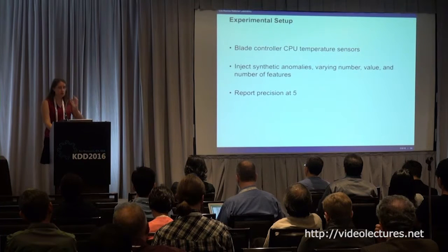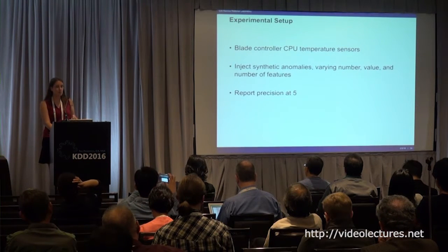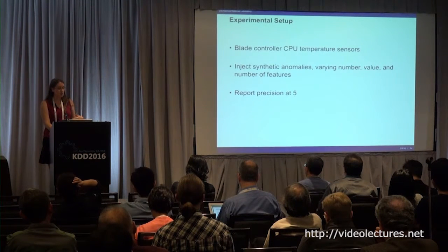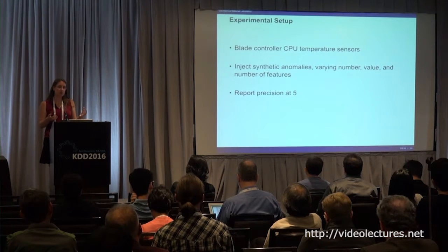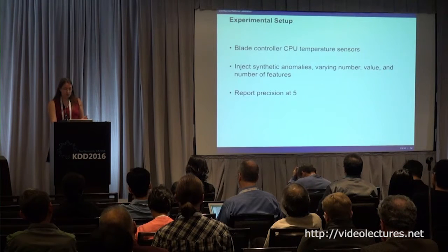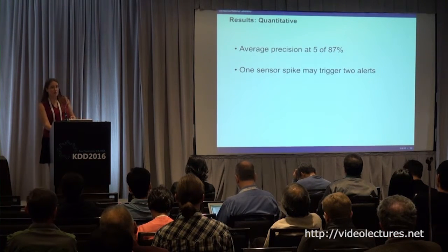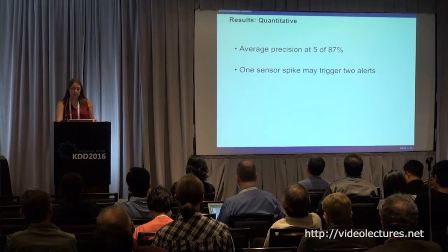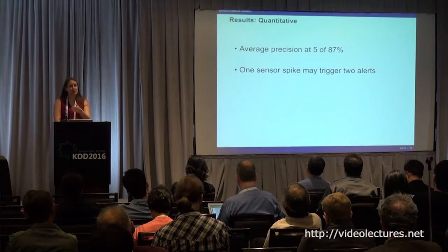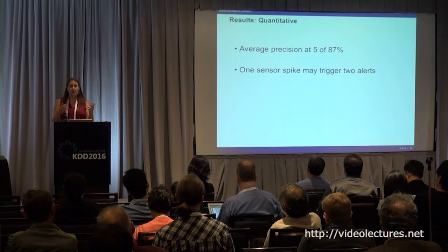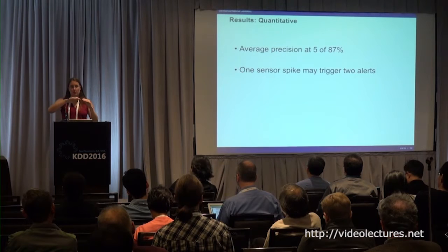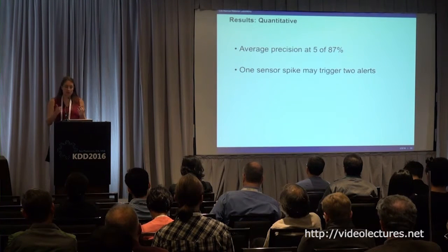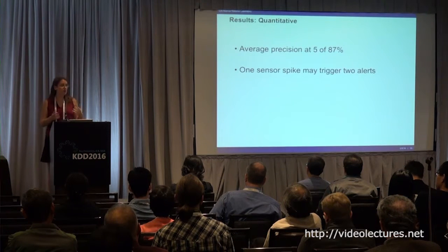We ran some experiments on data from Trinity, specifically on the blade controller CPU temperature sensors. We injected a few synthetic anomalies, varying the number of anomalies, the values making a data point anomalous, and the number of features — meaning the number of sensors giving an injected anomalous reading. We report precision at five. We get an average precision at five of 87% on these injected anomalies, which is pretty good. We also notice that one spike in a sensor can trigger two alerts because we include temporal features — both raw features and the deltas between each time step — so the delta going up and coming back down can cause two alerts.